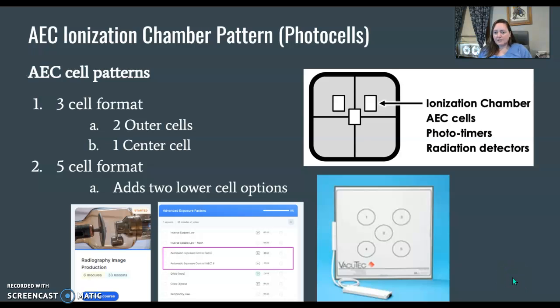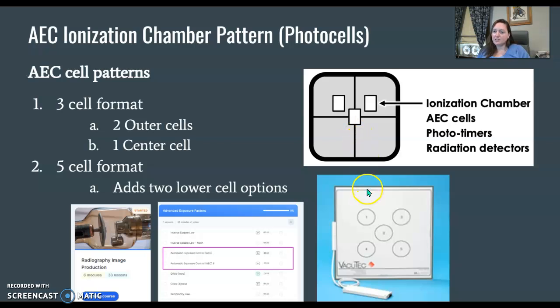The photo cells — which is an old term, we're using ionization chambers now — is something you might also see or hear techs at a facility call them. If you look on the outside of your bucky, it's either going to be a three-cell format or a five-cell format. Most older machines only have three — a two-outer, one-center-cell setup, which is the most common. Some newer machines have a five-cell option: two outer upper ones, two lower, and then still a center cell.